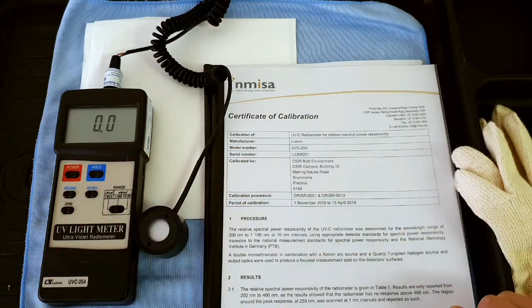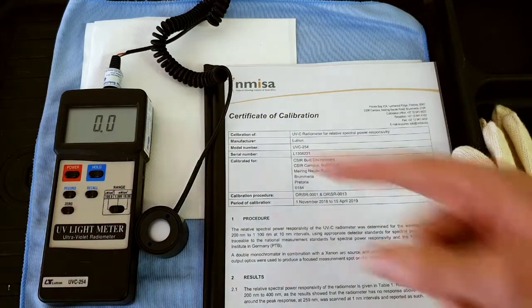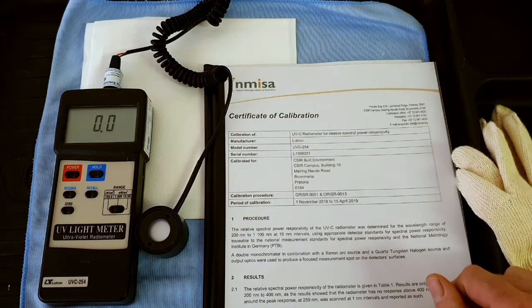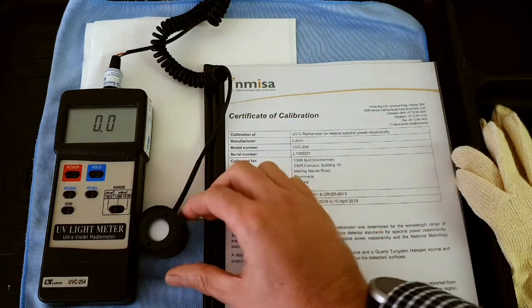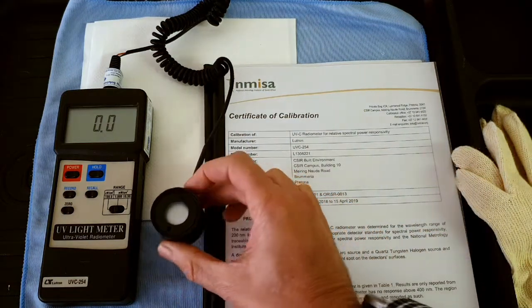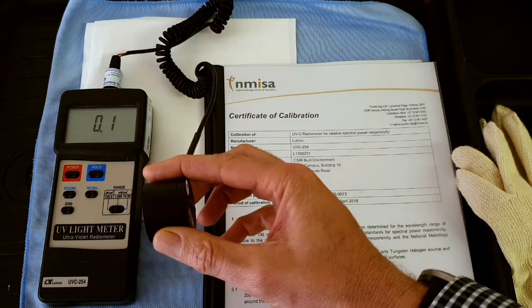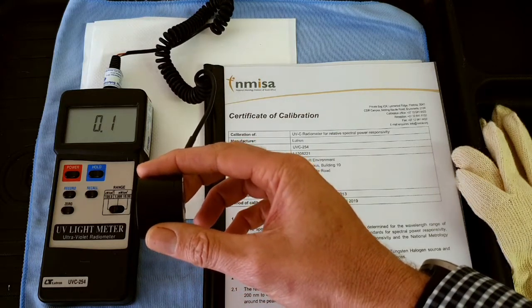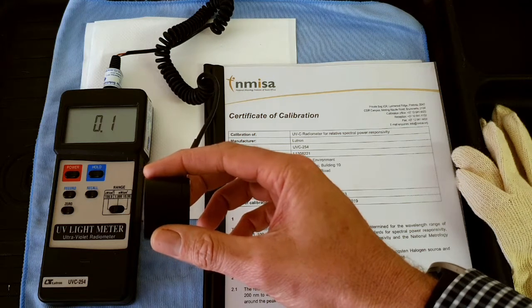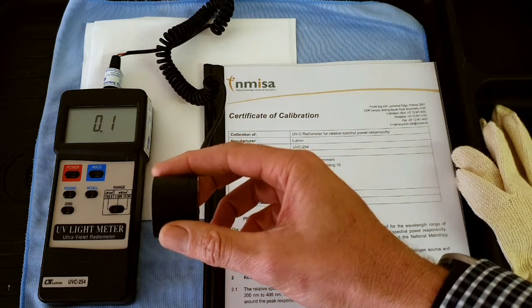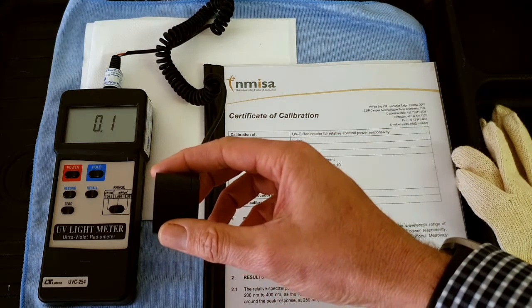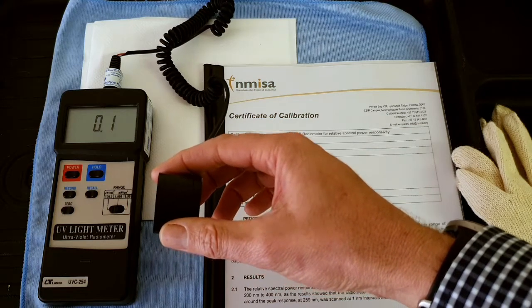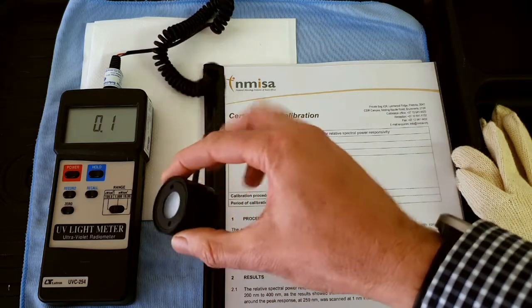All right, so I've got an open window just next to me over here. That's probably why you can hear the traffic at the moment. And if I tilt the sensor towards the window, you can see there's some response. So it's reading 0.1, it's claiming to read 0.1 microwatts per centimeter squared of UVC when we know there's no UVC in the room at the moment.